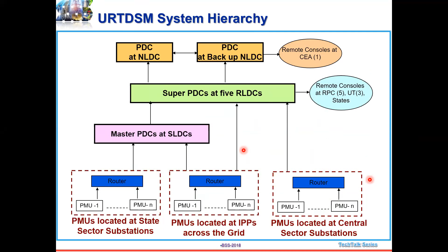So this is the basic PMU installation. It's basically very compact. Earlier it used to be very big. Nowadays it is available in simple 19U racks like any other numerical relay. Even the protection relays are having PMUs nowadays, but with lesser capability. Normally PMUs will have 256 samples per second data sampling, but the relay-based PMUs will have around 128 samples per second. Anyway, that is more than sufficient for our purpose. So this is what we are having.